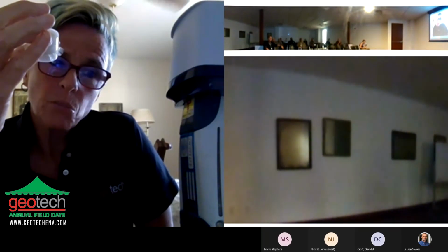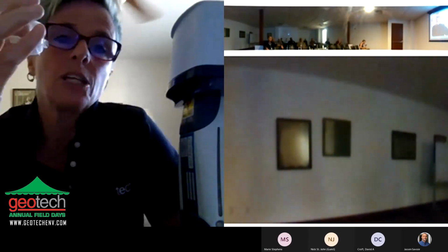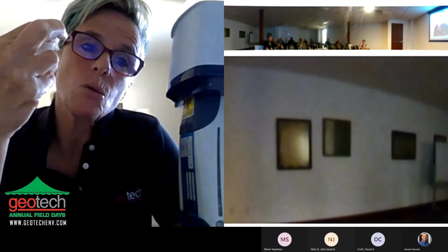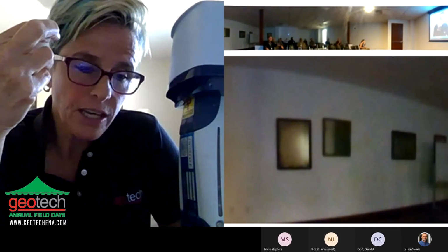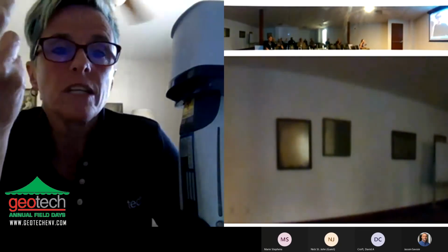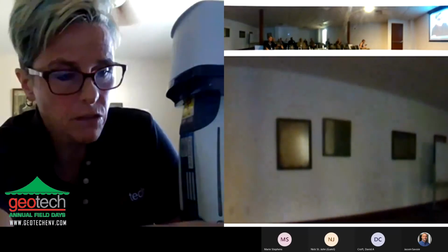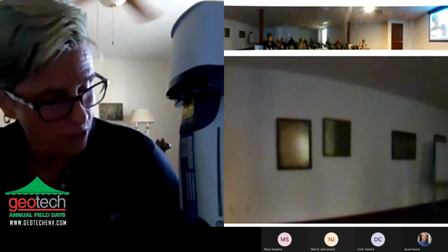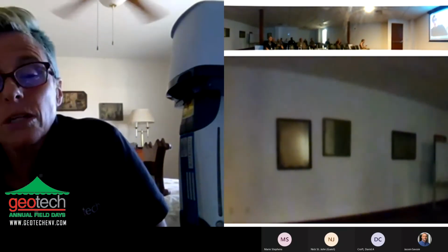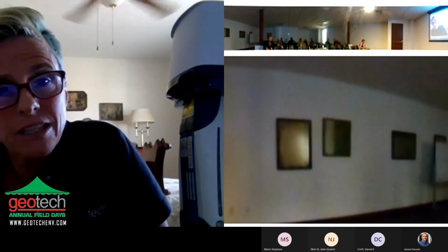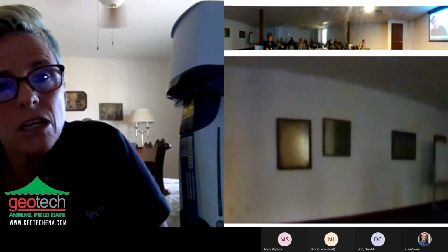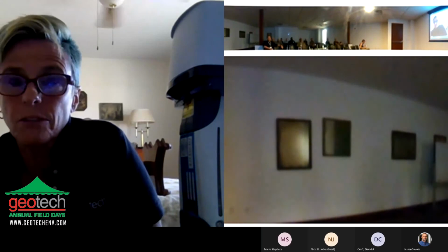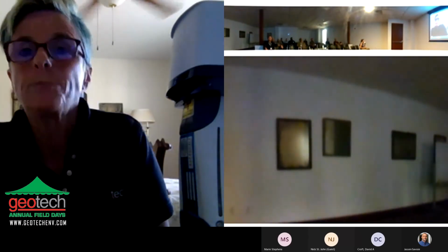But what's important is what's coming back to the detector. You might be able to excite things down an inch or two, but those aren't going to come back. So usefully, you're able to penetrate about 3/4 of an inch for a soil sample based on the density of it. As well as if you're dealing with plastics for a consumer product safety commission type of application, your plastics tend to be not very dense at all. So there's a lot more backscatter and you're penetrating through most of the plastic with that. Is that sufficient? Yes, thank you. Okay, excellent.